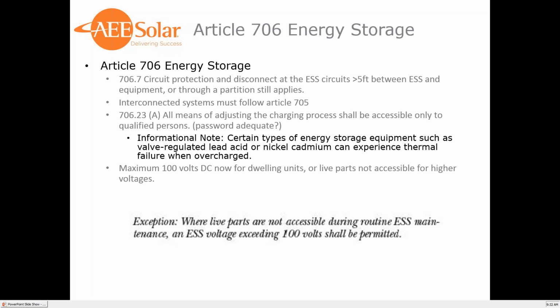706.23a, all means of adjusting the charging process shall be accessible only to qualified persons. There's not really too much clarification on this. Is a password adequate to prevent somebody that's not qualified from going through the system? I put an information note from the code that it looks like they want to implement this because certain types of energy storage, such as valve regulated lead acid or nickel cadmium, can experience thermal failure when overcharged. So if it's password protected, does that mean that would be adequate and the AHJs will allow that? I think that one's going to be up for interpretation.